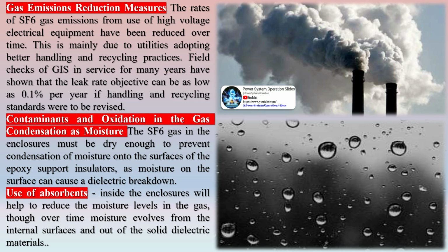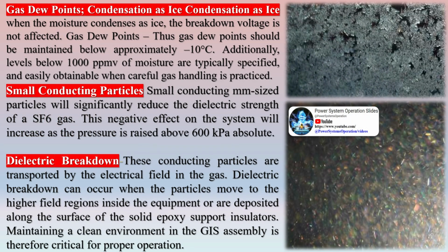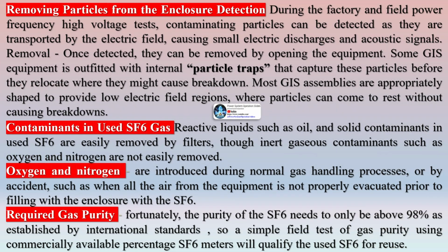Inside the enclosures will help to reduce the moisture levels in the gas, though over time moisture evolves from the internal surfaces and out of the solid dielectric materials. When the moisture condenses as ice, the breakdown voltage is not affected. Thus gas dew points should be maintained below approximately -10 degrees Celsius. Additionally, levels below 1000 ppmv of moisture are typically specified, and easily obtainable when careful gas handling is practiced.